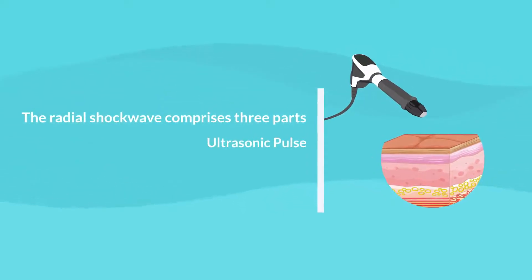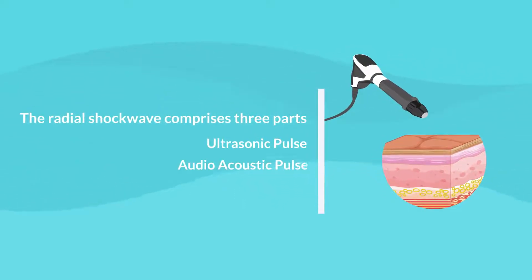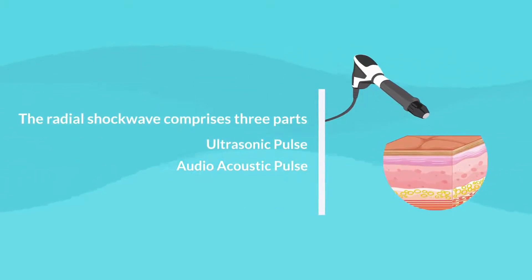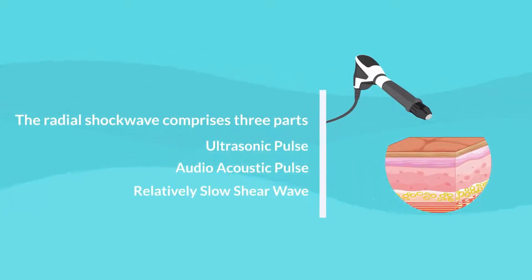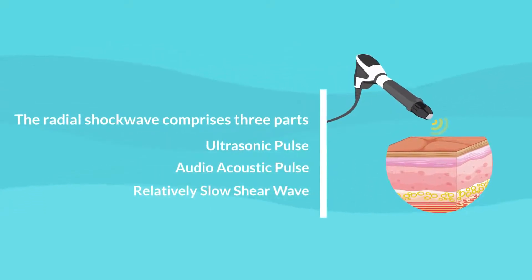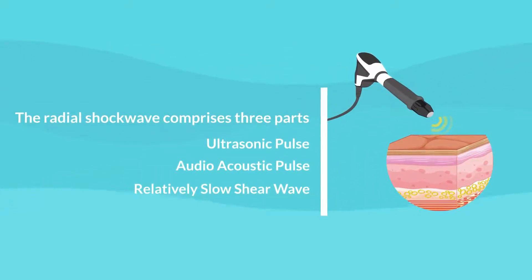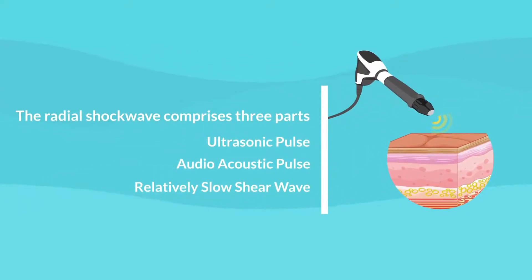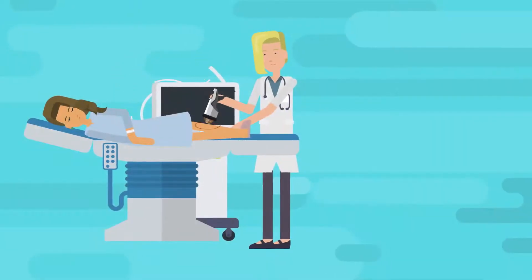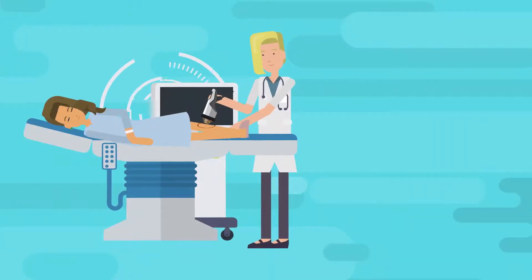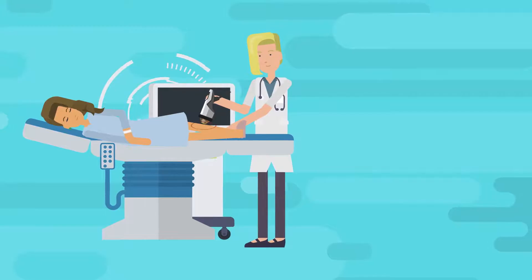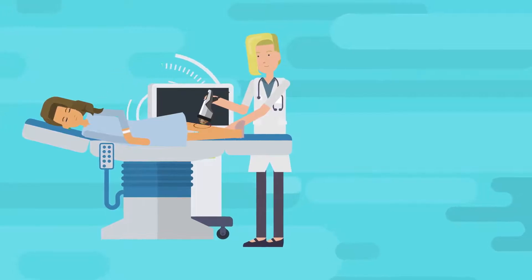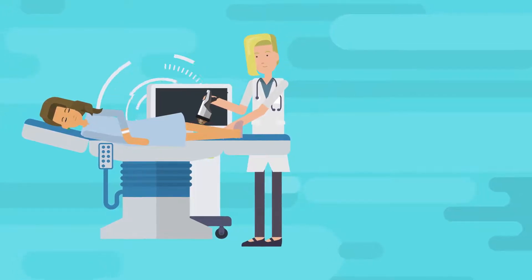Here's how they both work. The radial shockwave comprises three parts: the ultrasonic pulse, audio acoustic pulse, and the relatively slow shear wave. The pressure waves lose power the deeper they enter the body. Focused shockwaves, however, can penetrate deeper into the tissues and deliver all of their power at the designated depth.